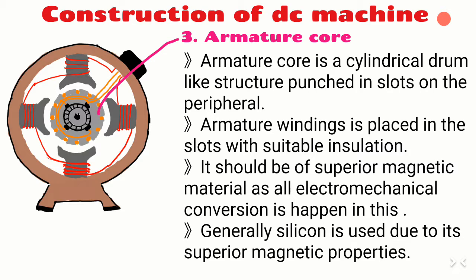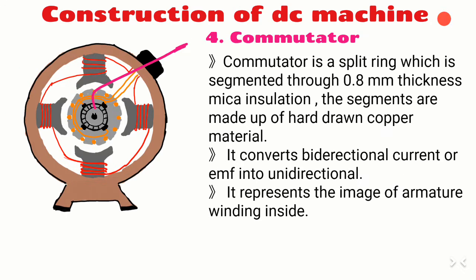The commutator is a split ring segmented with 0.8 mm thick mica insulation between segments. The segments are made of hard-drawn copper material. It converts the bidirectional current or EMF inside the coil into unidirectional output. It represents the image of the armature winding. The number of commutator segments is equal to the number of coils.